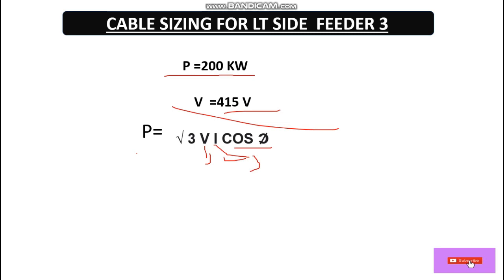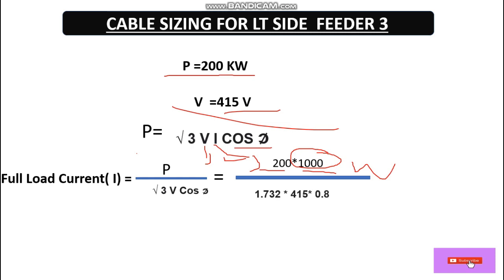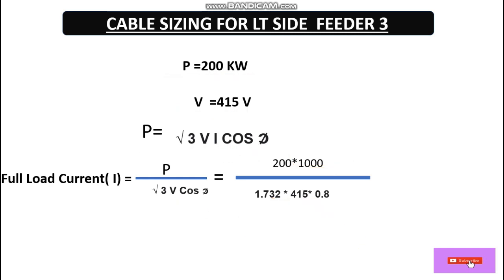Now let's calculate the full load current. The formula gives I = P ÷ (√3 × V × cosφ). Putting in the values: power is 200 kilowatt converted to 200,000 watts, divided by √3 (which is 1.732) × 415 volts × 0.8 power factor. After calculating, the full load current value becomes 348 amperes.